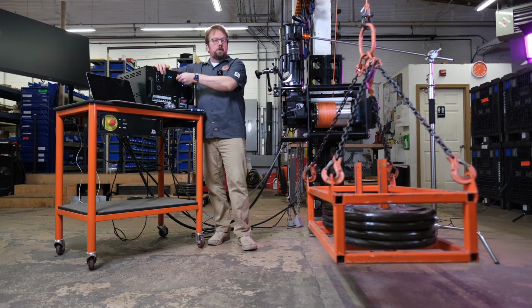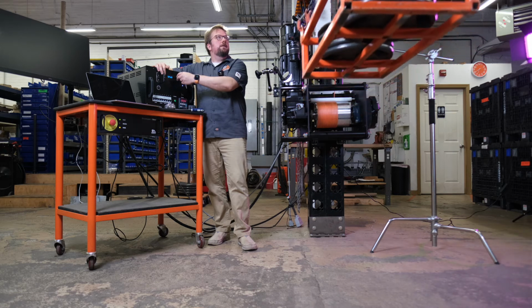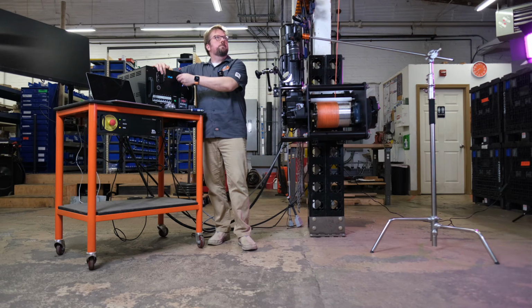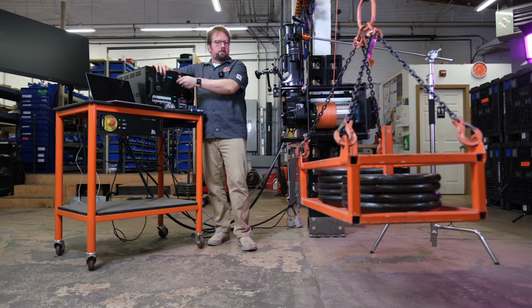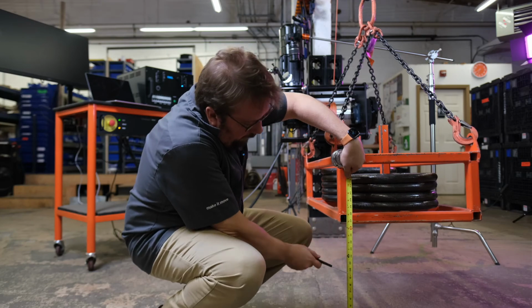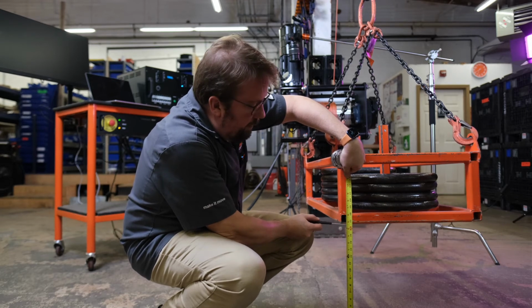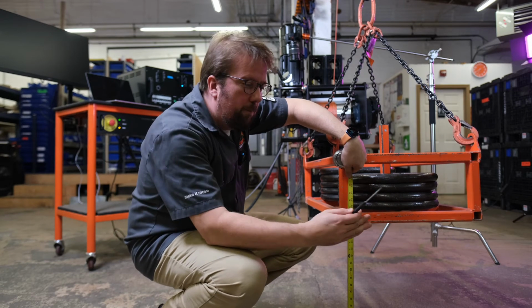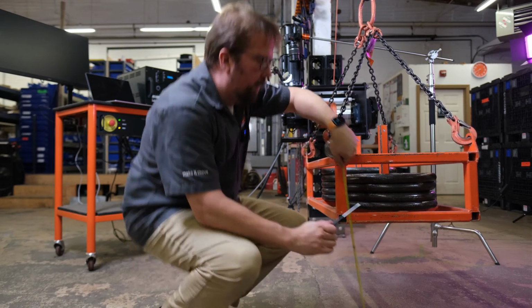And now we got to run the hoist back up so we can check and see how we did. Now this time I won't stop it, I'll let the limit switch stop it. Whoa! I wanted to be down here, and instead I stopped up here. That means that I'm hitting the switch too early. I've bumped that cam into the switch too aggressively, and I need to back it off a little bit.